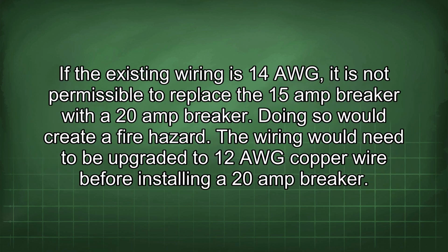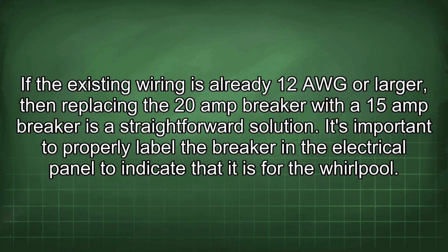If the existing wiring is 14 AWG, it is not permissible to replace the 15 amp breaker with a 20 amp breaker. Doing so would create a fire hazard. The wiring would need to be upgraded to 12 AWG copper wire before installing a 20 amp breaker. If the existing wiring is already 12 AWG or larger, then replacing the 20 amp breaker with a 15 amp breaker is a straightforward solution.